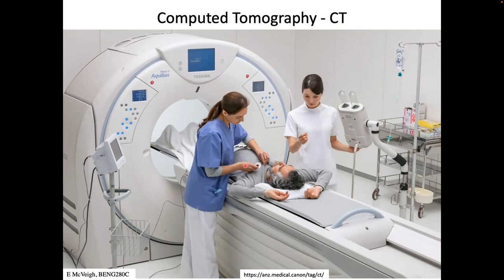Depending on what anatomy you want to image, there's a set of laser lights to align the patient. Scout scans are performed first: you run the patient through the bore while the gantry rotates and take a low-dose projection picture to see where the diaphragm and heart are. These are then used to align the scan to first order.